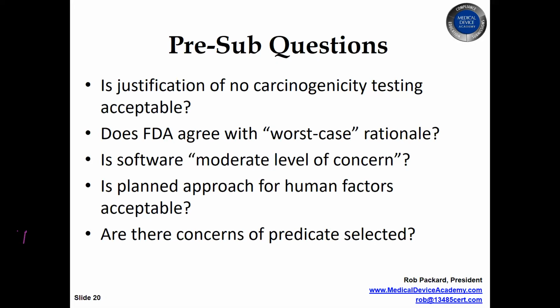If you are trying to come up with a justification for why you don't have to do some of the EMC testing because it's so small and barely emits any power, and because of the way it's going to be used and the environment of use, you might be able to get out of some of that EMC testing. If you're asking specific questions about the software, or cybersecurity, what kind of level of traceability the FDA wants, is it a moderate level of concern or is it a minor level of concern? You always think it's minor, the FDA always thinks it's moderate.